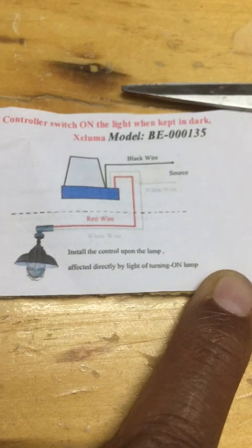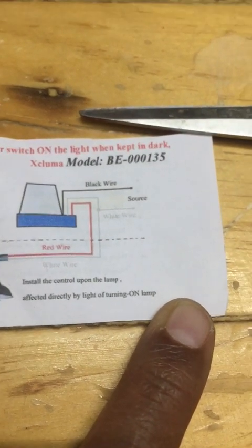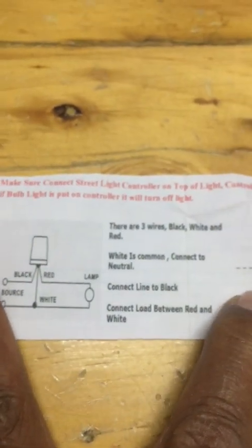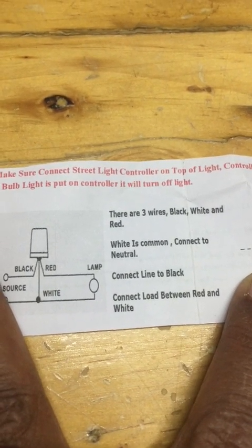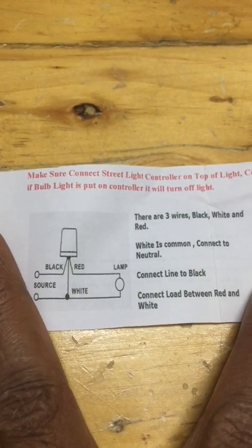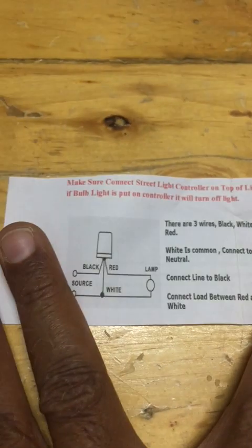Here we can find all three wires and there is a diagram also. This is how we have to connect to the lamp. Model number is BE-000135 and the manufacturer is Xcluma. There are three wires: black, white, and red. White is common, connect to neutral; connect line to black; connect load between red and white.